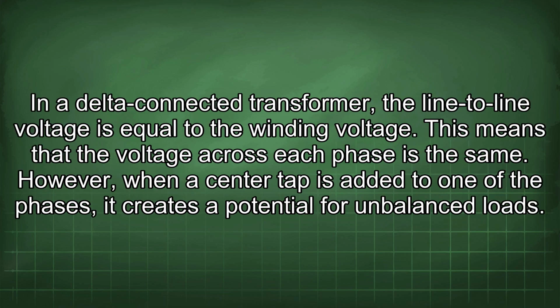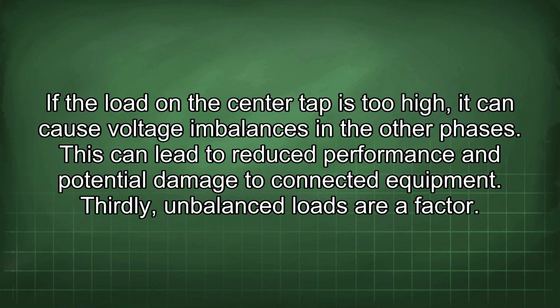In a delta-connected transformer, the line-to-line voltage is equal to the winding voltage. This means that the voltage across each phase is the same. However, when a center tap is added to one of the phases, it creates a potential for unbalanced loads. If the load on the center tap is too high, it can cause voltage imbalances in the other phases. This can lead to reduced performance and potential damage to connected equipment.